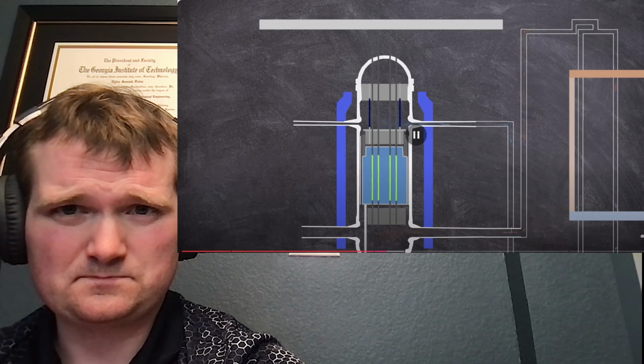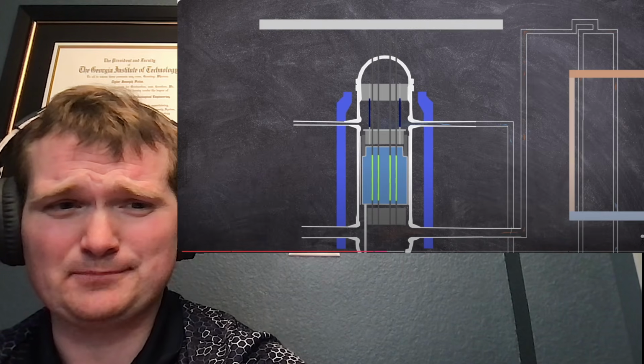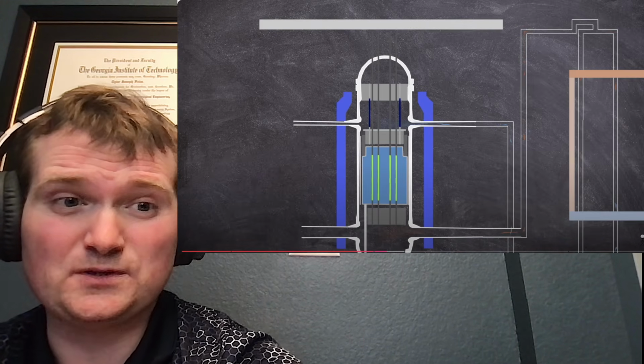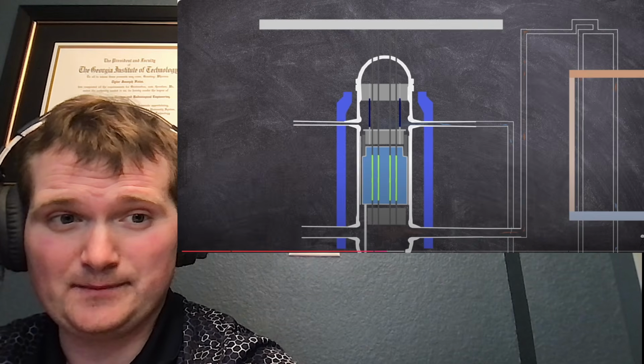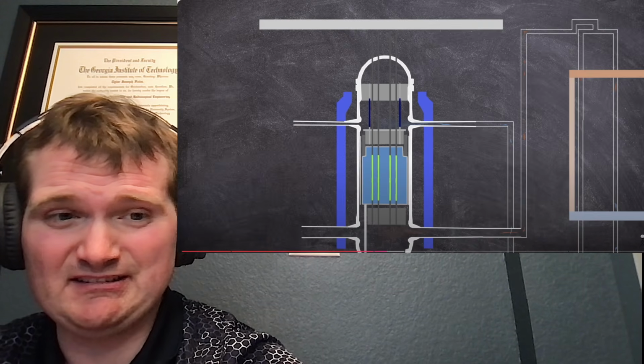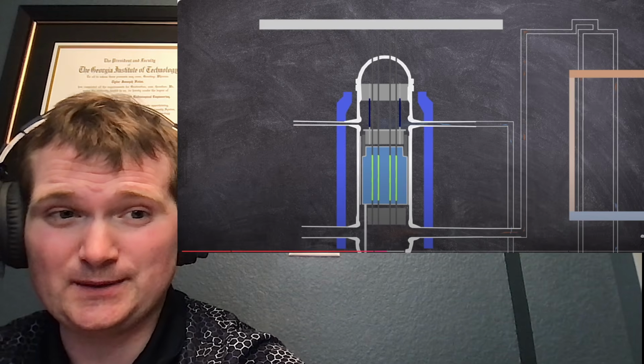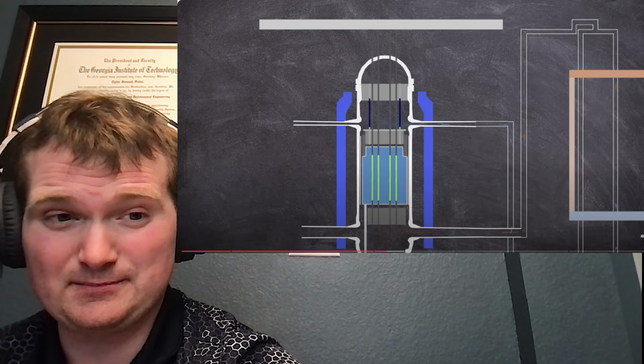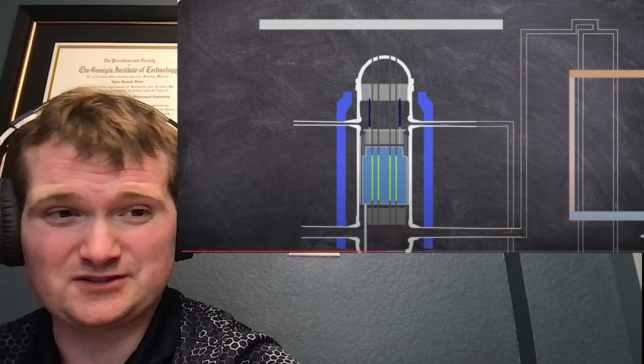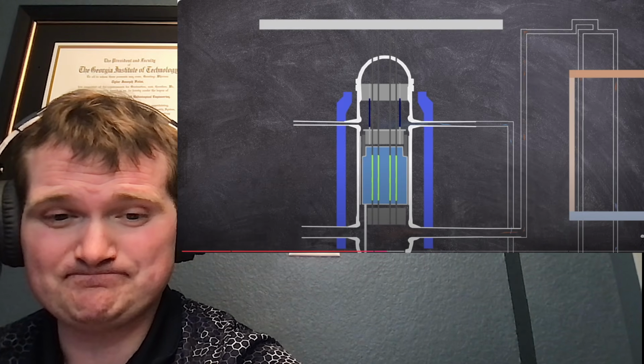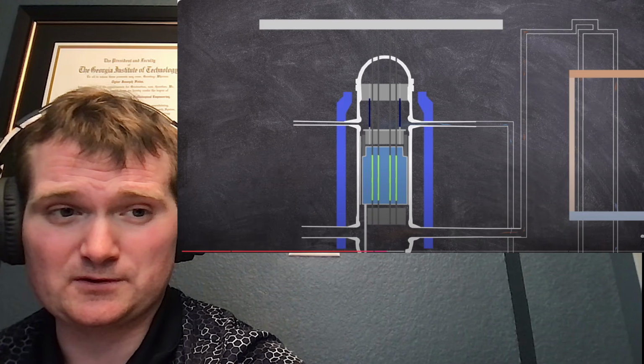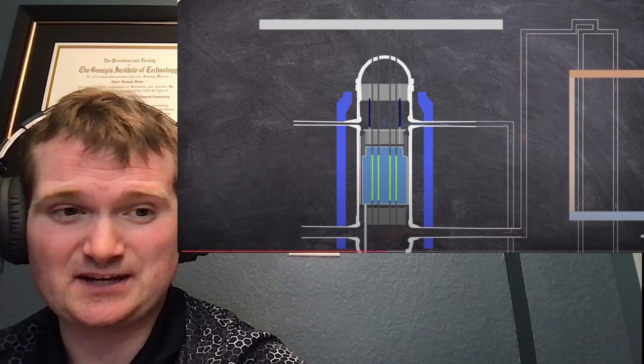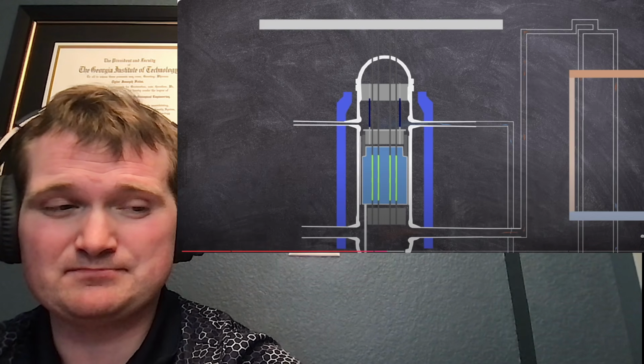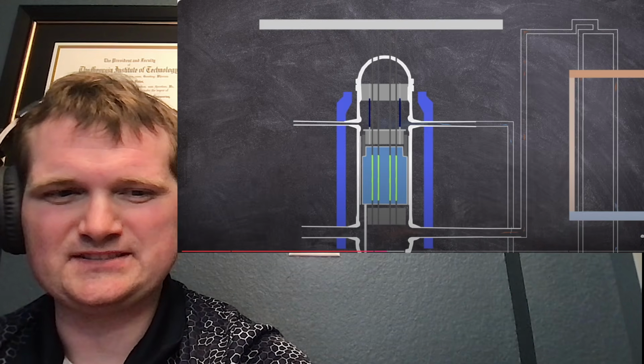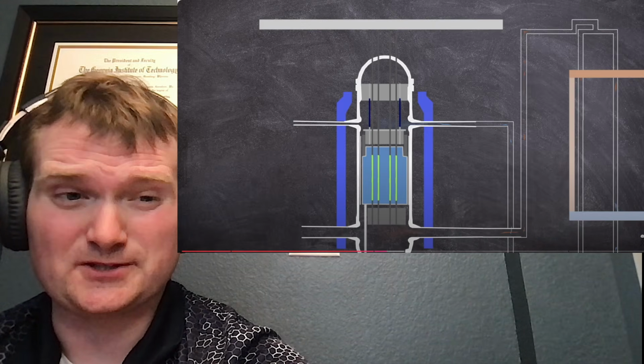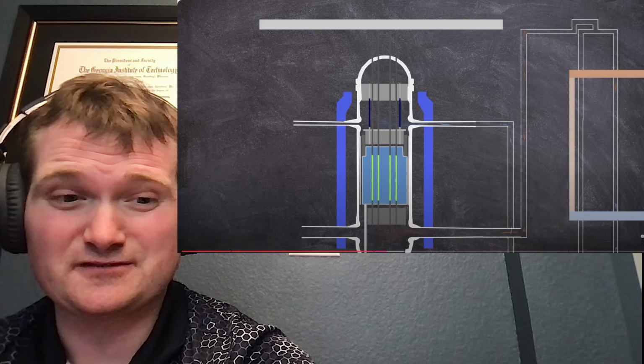The blackout. So 220 kilovolt, that's the off-site power source, the switch yard, if you will. You have the main turbine with, let's just say, an output voltage of 20 kilovolts, and then it goes to the main transformer, which steps it up to 220 kilovolts or what have you, to put the power out on the grid for long-range transmission, and then it gets stepped back down before it supplies whatever city it's supplying. So basically an issue with the switch yard or the transmission lines or something like that caused the fault.